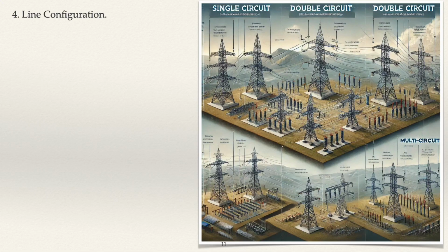Single circuit consists of 3 conductors for 3 phases, or 6 for bundled configurations. It is used for moderate power demands or lower voltage levels, and is simpler to construct and maintain. Double circuit consists of 2 sets of 3 conductors, or 6 bundled conductors per circuit, used for high power demands or to optimize transmission capacity in limited corridors. It offers redundancy and operational flexibility.